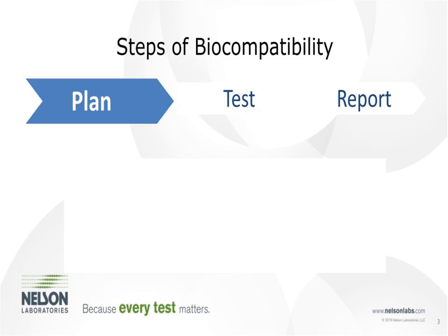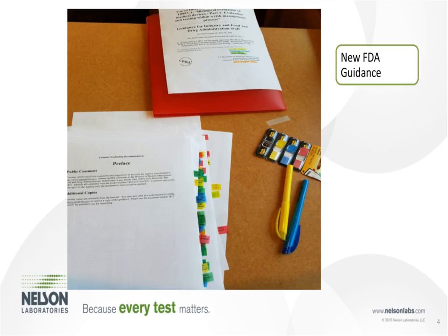There have been two main things that have happened recently that really stimulated this type of approach with biocompatibility. The main one happened in June, and that's this guidance document that hopefully you all are familiar with. This guidance document was released by the FDA in June. It was a finalization of a draft document that came out in 2013.